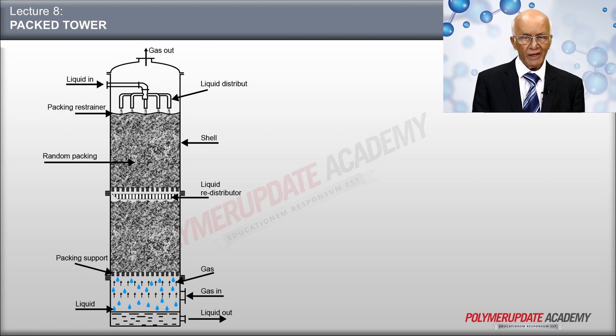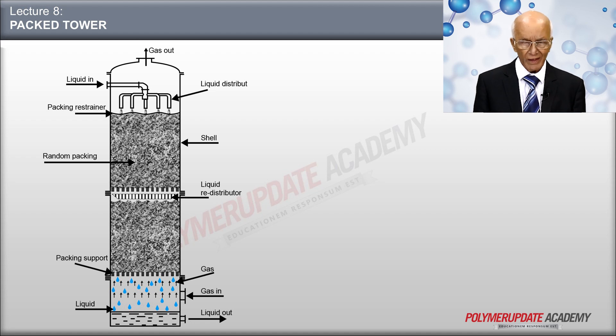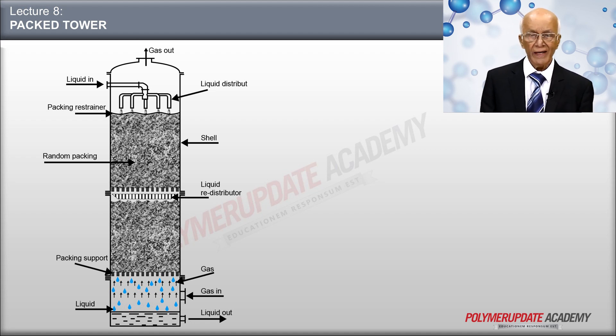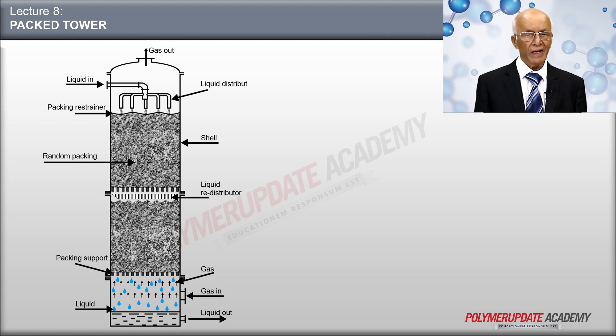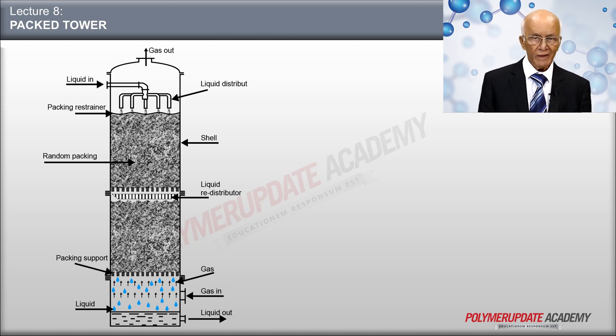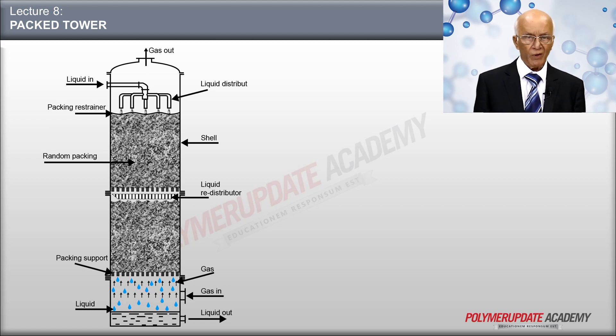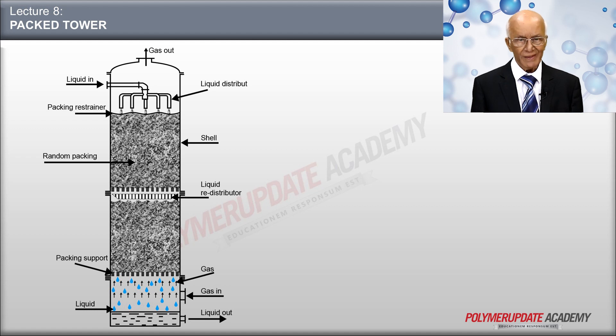After a certain height, there is a liquid redistributor, because packing loses its efficiency after a certain height. As we go above, there is a packing retaining grid, because sometimes due to a surge in gas velocity, packing may be carried away from the column. Above that, there is a packing support grid over which there is a liquid distribution system, and then we have a gas outlet.